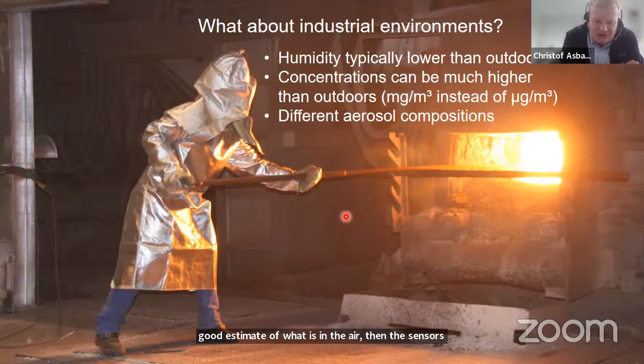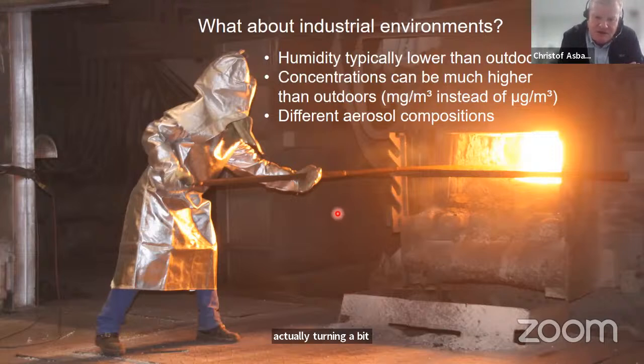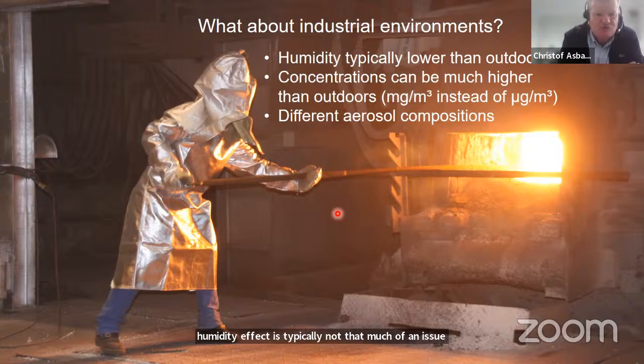Okay, but I mentioned also in the beginning that we're currently a bit more interested in looking at what's happening indoors, because there, especially the humidity effect is typically not that much of an issue, because you have lower humidity levels indoors than outdoors, especially not the high peaks. But concentrations can be much higher than outdoors, especially in industrial environments. The other downside is that, whereas for outdoors the sensors are already calibrated for the ambient measurements, although it may not be fully sufficient, as we've seen, for indoors they're definitely not calibrated, so they need to be recalibrated.